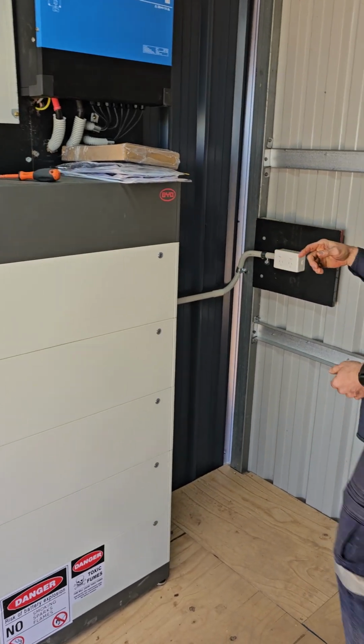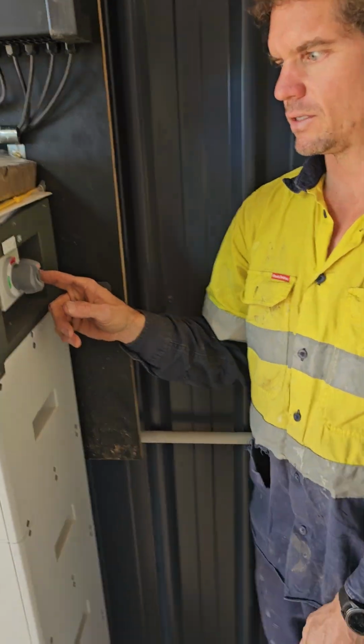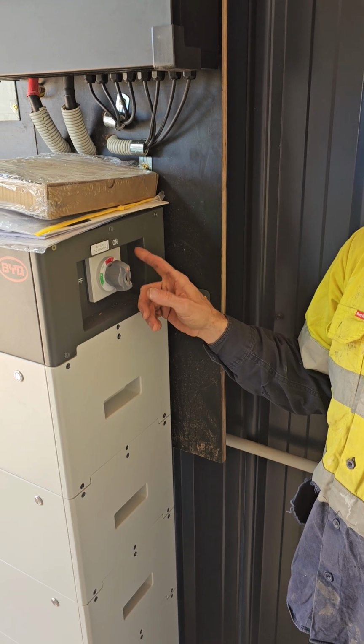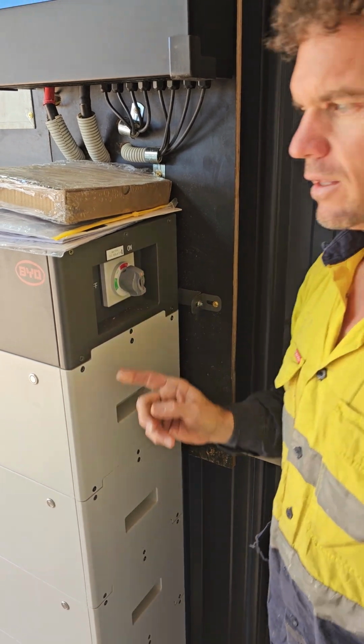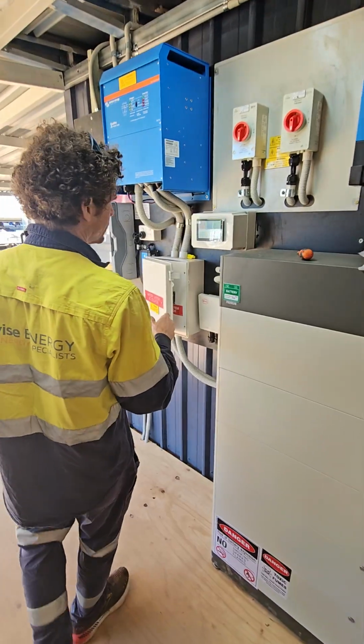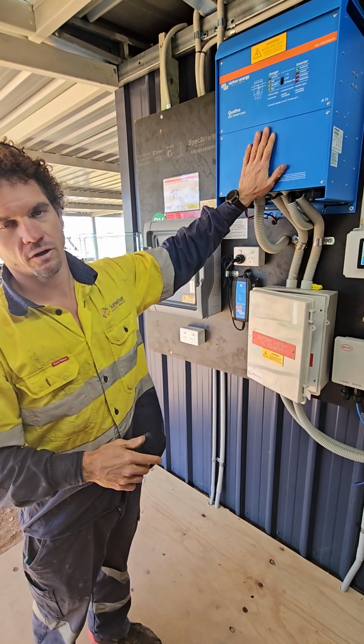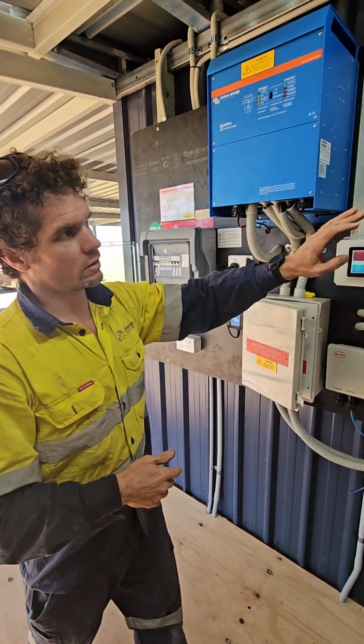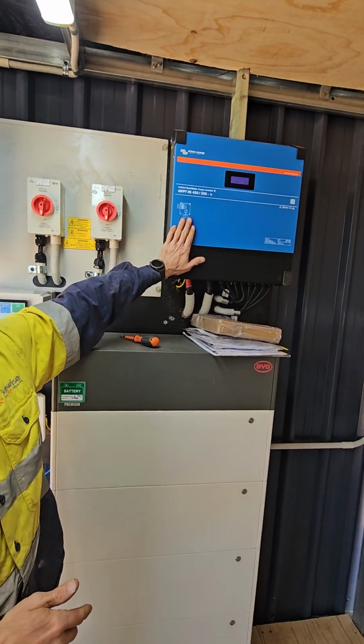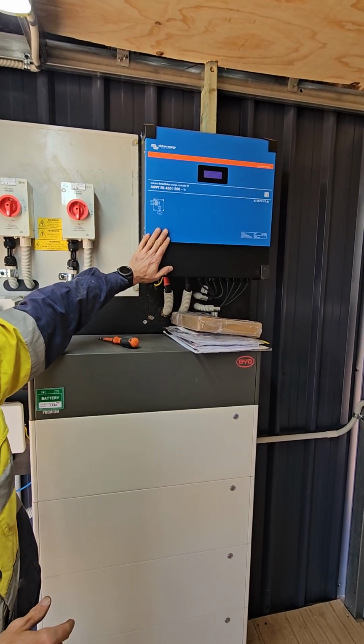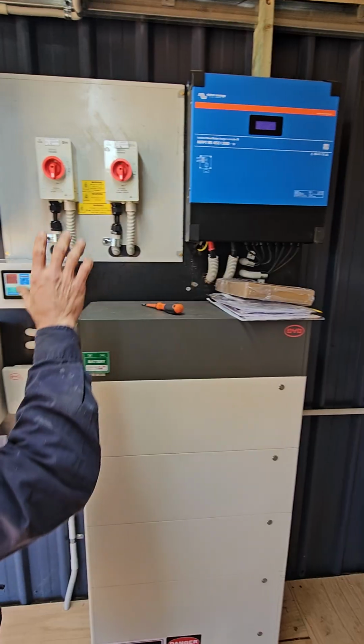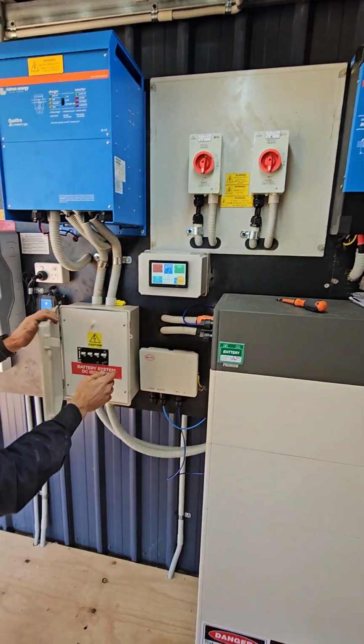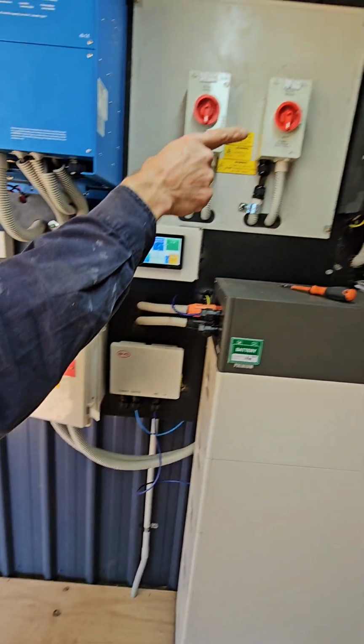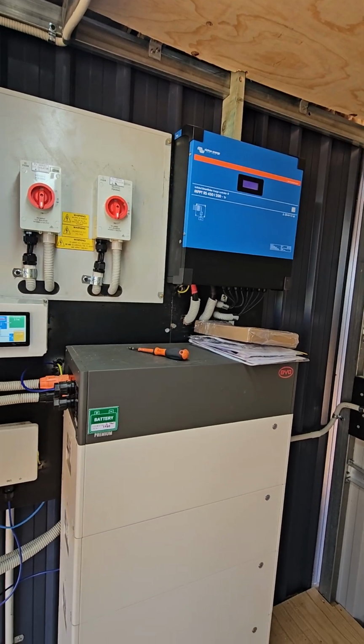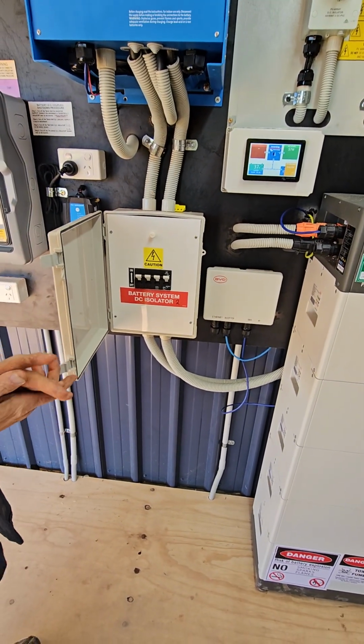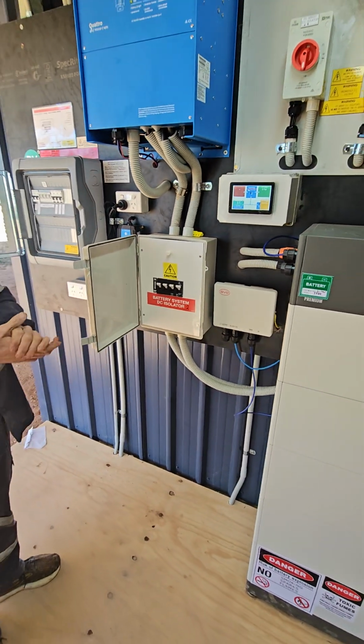If you come around to the side here, you'll see battery system DC isolator number 1. This is your first battery isolator, and you also have a second because we need to isolate this battery inverter and your solar inverter, which is directly coupled to the battery, separately. So this main isolator will isolate both, and this one will just isolate the solar inverter. That's what the two isolators do as part of the procedure.